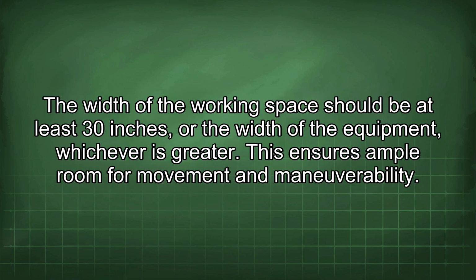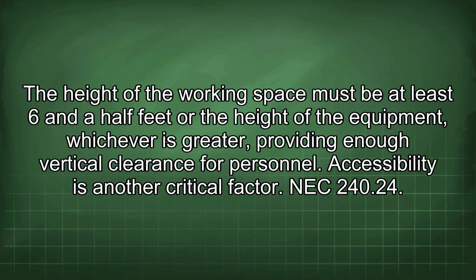The width of the working space should be at least 30 inches, or the width of the equipment, whichever is greater. This ensures ample room for movement and maneuverability. The height of the working space must be at least 6.5 feet, or the height of the equipment, whichever is greater, providing enough vertical clearance for personnel. Accessibility is another critical factor.